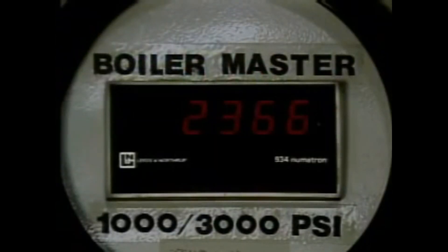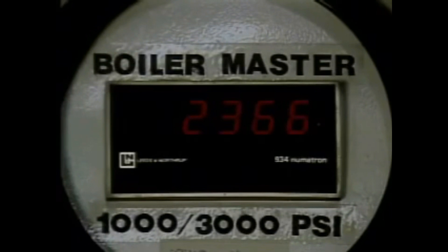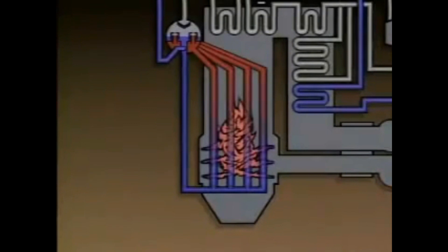Increasing pressure has a negative effect on natural circulation, because as pressure increases, the density difference between water and steam decreases. In some boilers, boiler water circulation pumps are used to increase circulation.